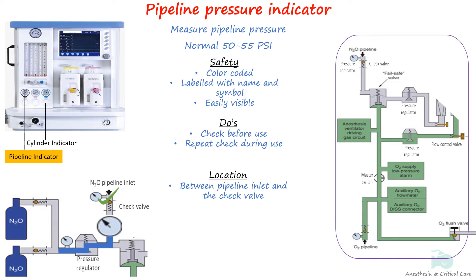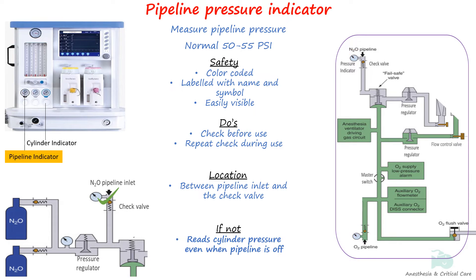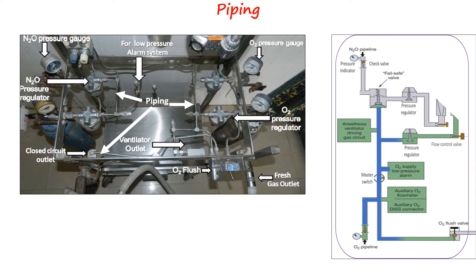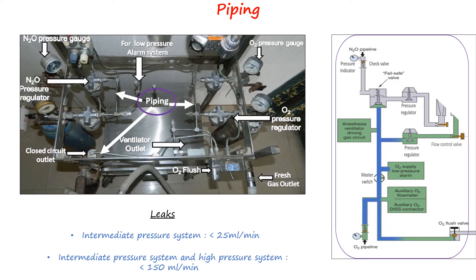If the indicator was installed downstream of the check valve, the gas flow from an open cylinder would be read by the pipeline indicator until suddenly the cylinder is exhausted. Piping consists of pipes used to connect components inside the machine. It must be able to withstand four times the intended service pressure. Leaks between the pipeline inlet or cylinder pressure-reducing system and the flow control valve should not exceed 25 milliliters per minute; if the yoke and pressure-reducing system is included, leakage may not exceed 150 milliliters per minute.